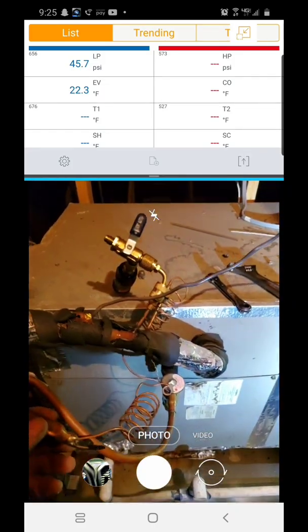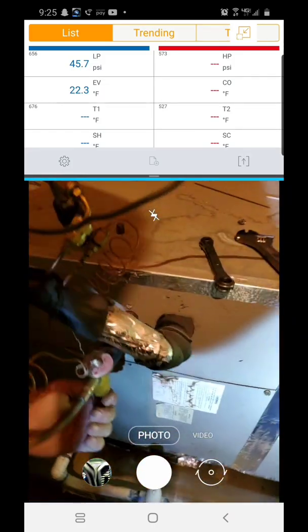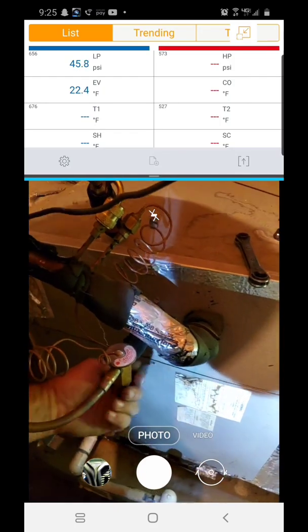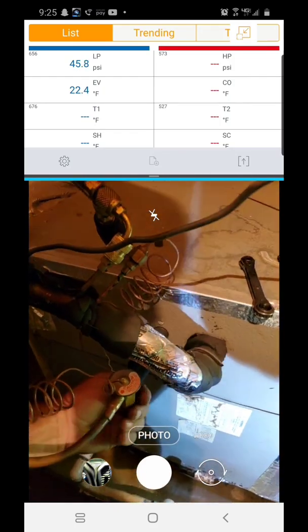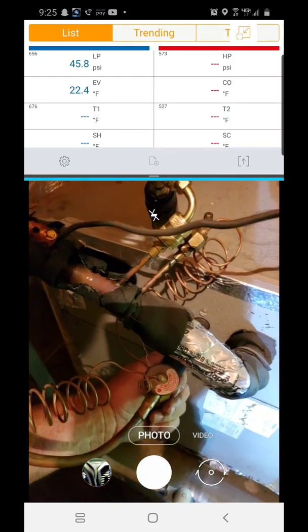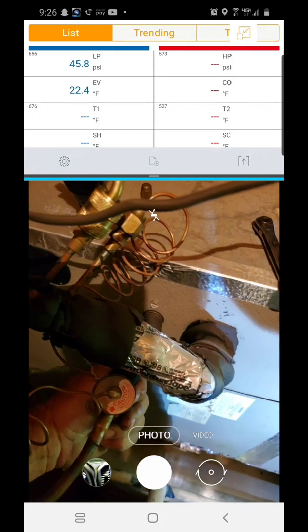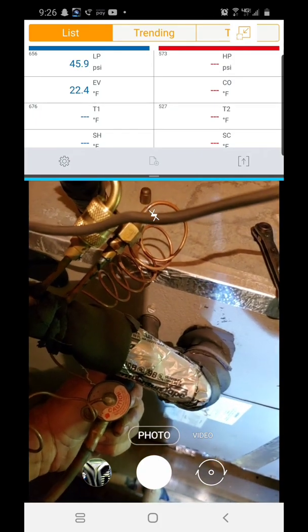Got this TXV - I'd already cranked open the valve all the way. Man, this thing's good and freezing cold. You can look, it's at 22 degrees.